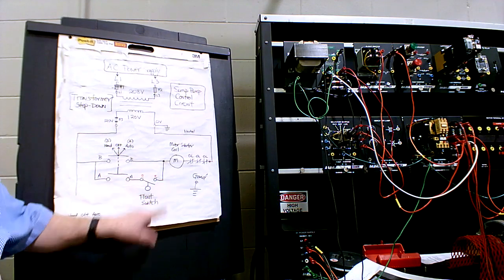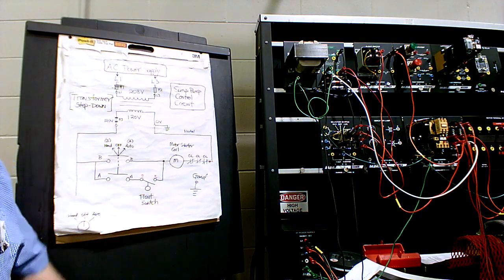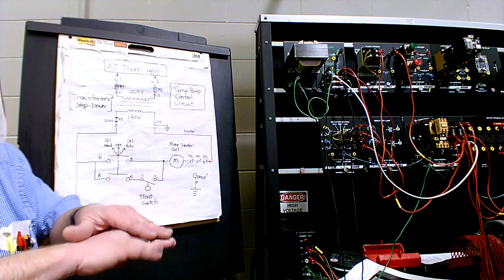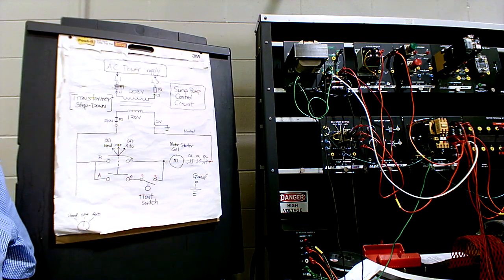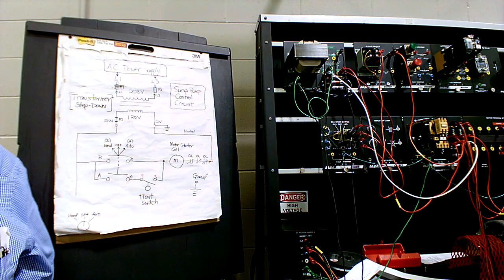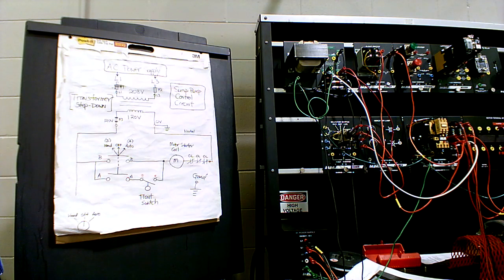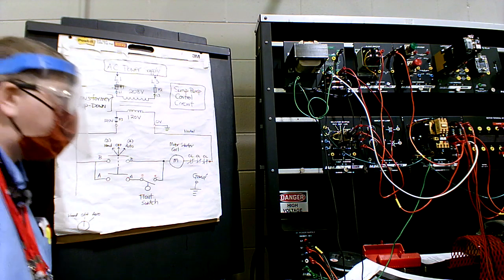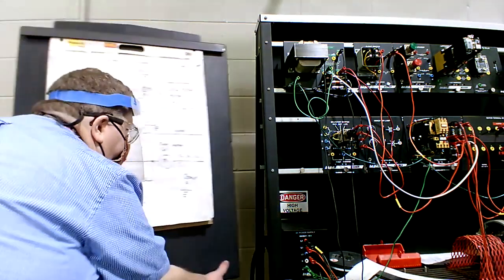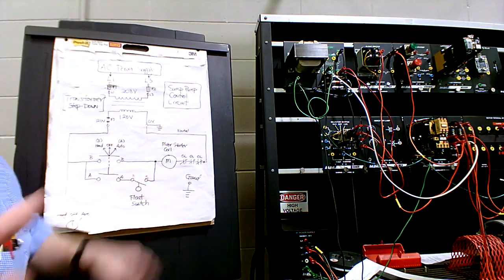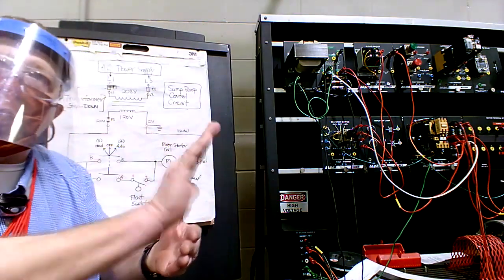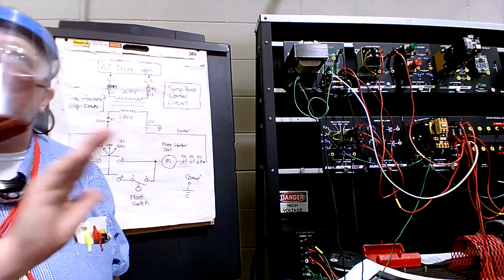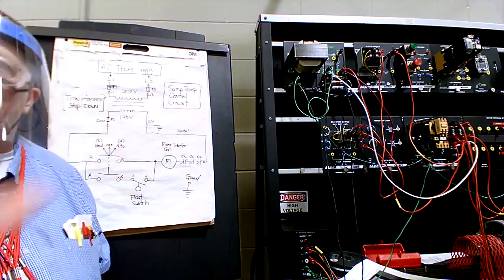So what's wrong? You've got a bad float. The float contacts have gotten corroded and it's gone bad. So what I did, I flipped the switch and made the contacts be bad. That's called low voltage. If you have a low voltage condition, when you have low voltage getting to the coil, low voltage is going to make it pull in, and it can't. It's going to chatter. It will chatter under low voltage like your vehicle does when your battery's weak.